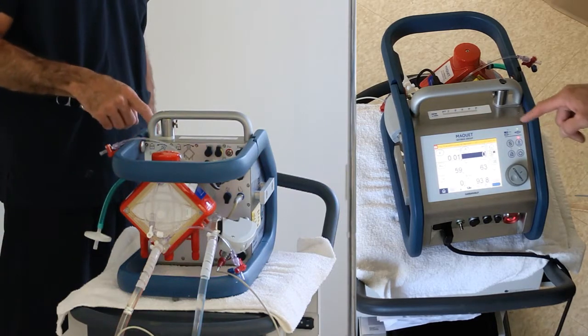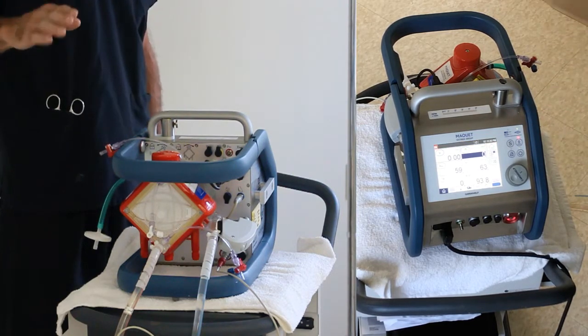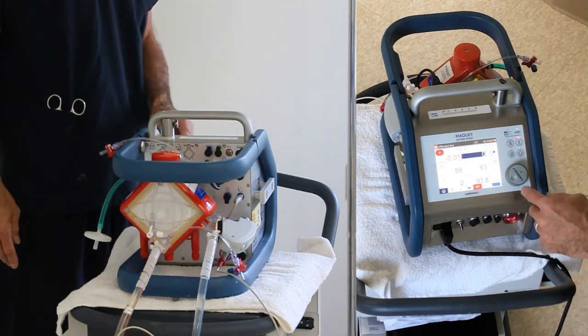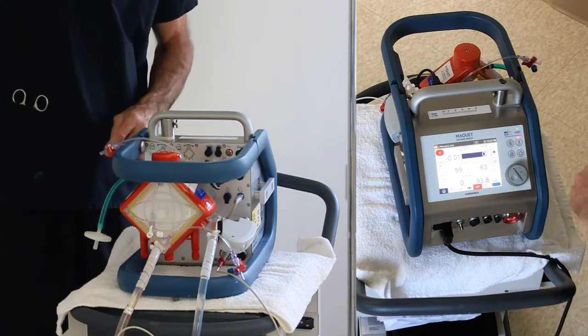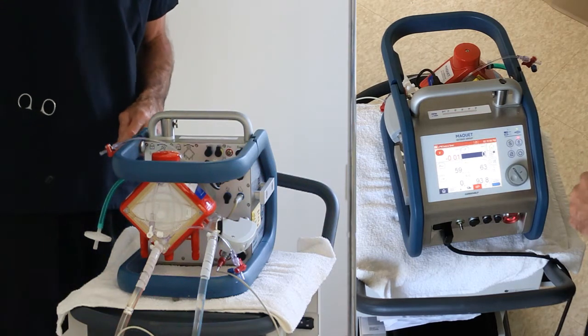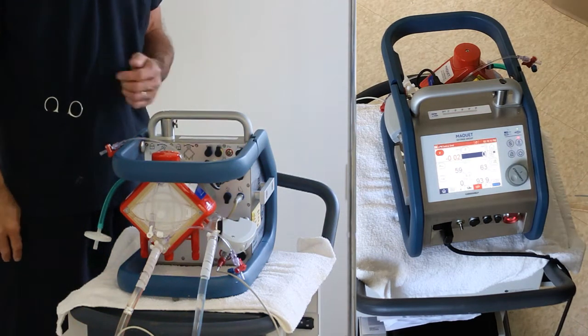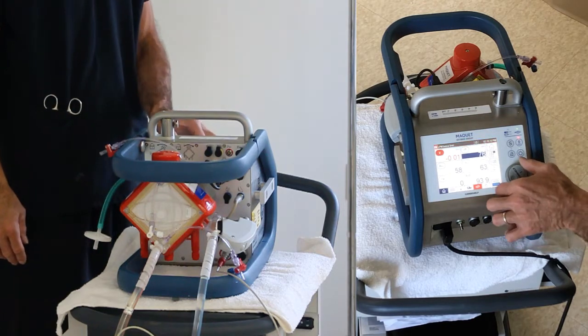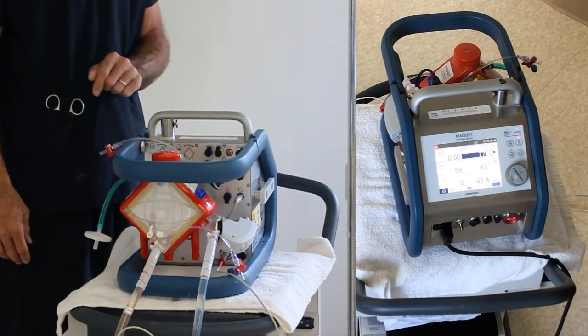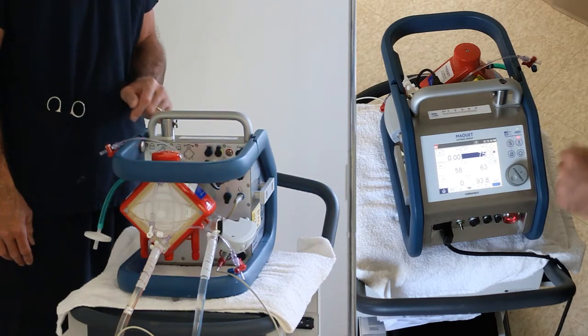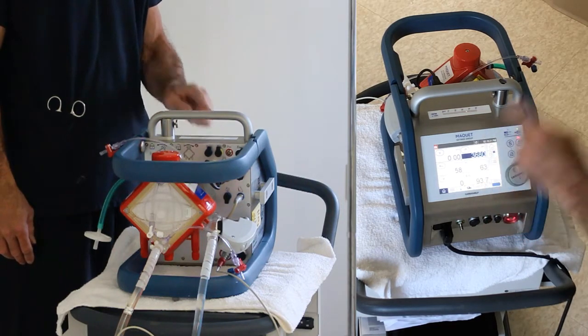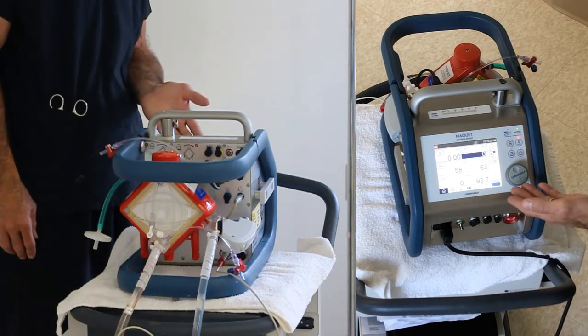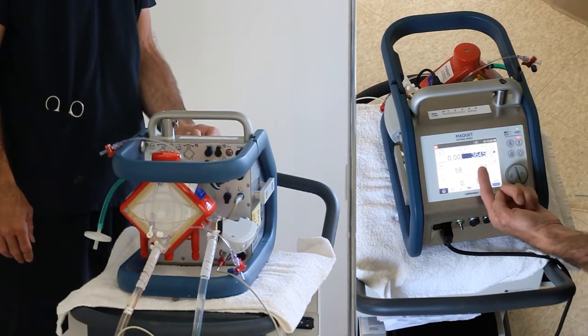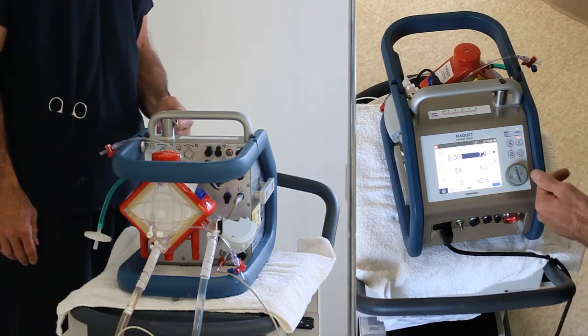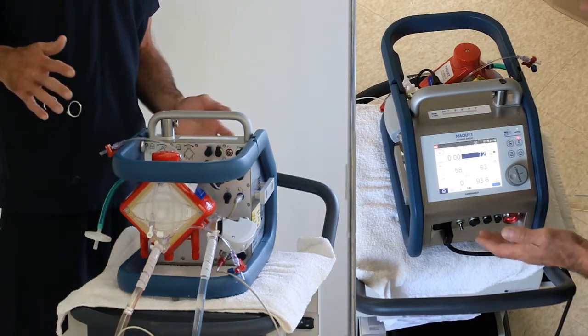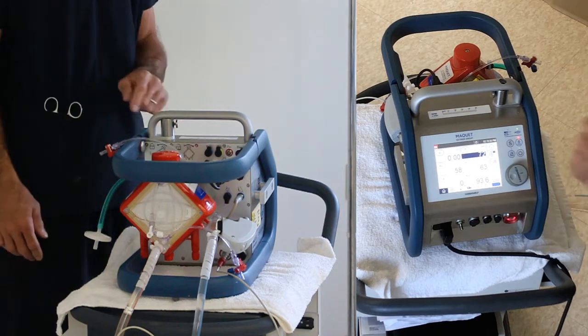And in this mode, the pump has permission to raise and lower its RPMs as needed to keep the flow at 0. But since we have a bag up here, and it's not pulsing back at the patient, it doesn't have to do anything other than turn its RPMs to 0. Look, right now it just threw up 77 RPMs. I can increase the RPMs. You see them turn gray. They go to 3680, but they pop back to 0. I can turn them down, the gray, 3645, and they pop back to 72. So it is right now kind of going between 0 and 70 because it's in zero flow mode.